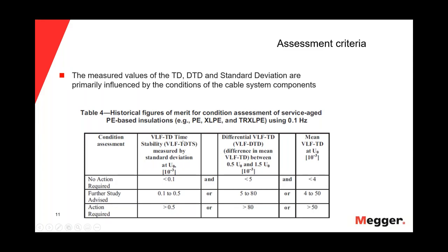And then VLF TD time stability would be, of course, the standard deviation. Less than 0.1, no action. 0.1 to 0.5, further study advised. And then, of course, greater than 0.5, action required.